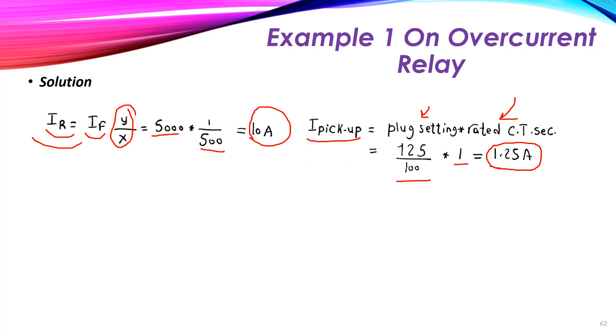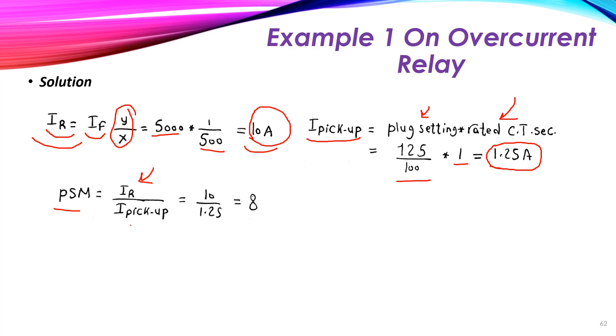We now have the relay-side fault current of 10 amperes and the pickup current of 1.25 amperes. The plug setting multiplier (PSM) equals the relay current divided by the pickup current: 10 ÷ 1.25 = 8. This is dimensionless — it means the fault current is 8 times the pickup current.